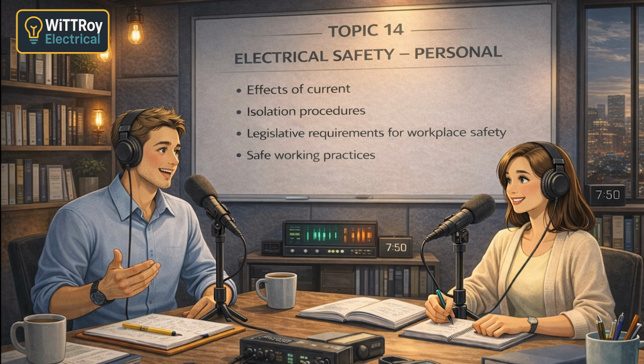What about safety tags again? Are there rules for removing them? Yes, usually only the person who applied the tag may remove it, unless a supervisor authorizes removal. That stops someone else making a mistake. Exactly. Now let's move into responsibilities under the law. That's under the Health and Safety at Work Act? Yes, employers, or PCBUs, must provide safe equipment, tools, PPE, training, supervision, and manage hazards and risks. And employees? Employees must take reasonable care of their own safety, not put others at risk, follow procedures, and use PPE provided.